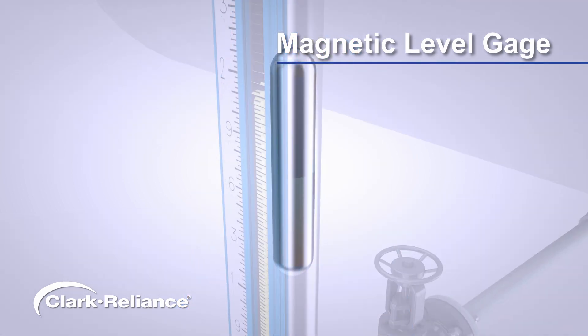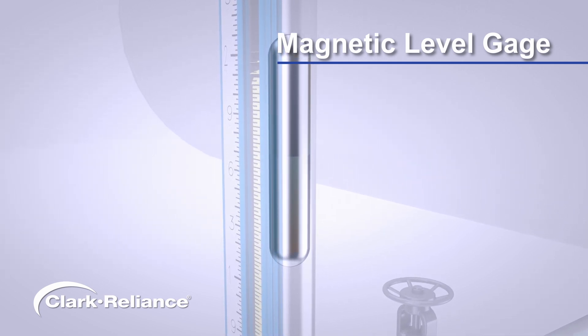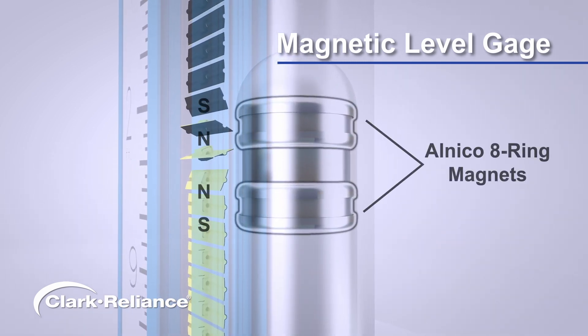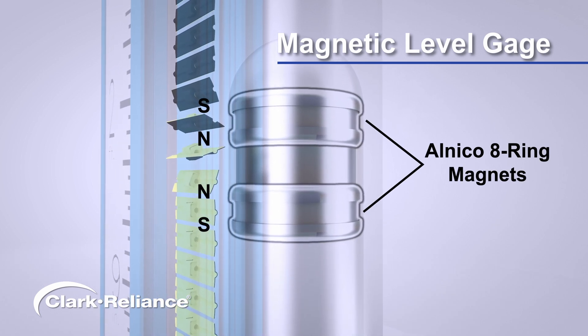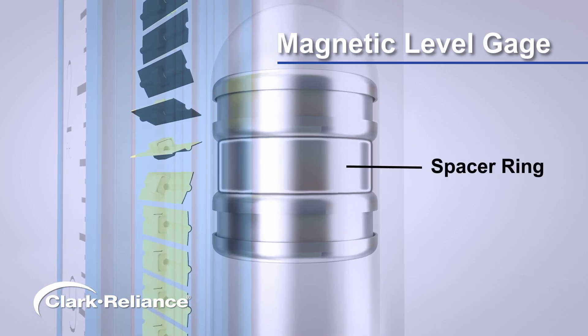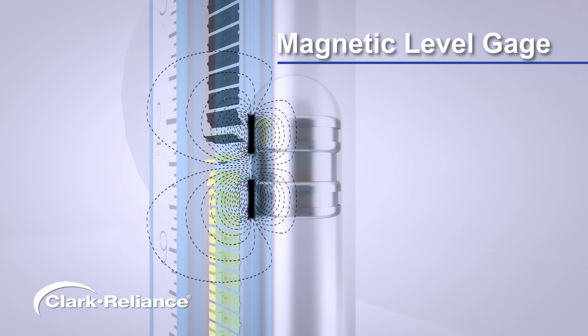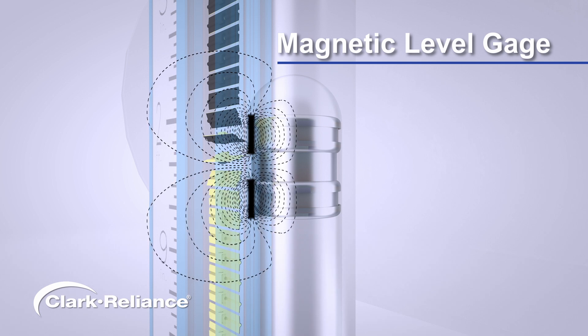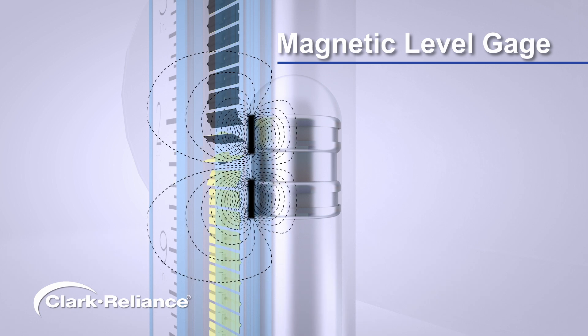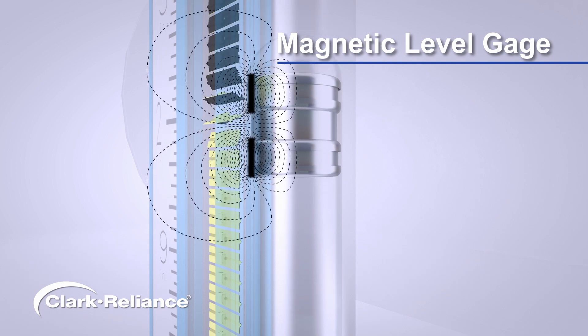The Jerguson float design features the strongest magnetic field of any magnetic level indicator, due to its unique construction. Two high-grade Alnico eight-ring magnets, with north poles opposing, are locked in place separated by a spacer ring. Magnetic flux flows from the north pole to the south, and since magnetic flux lines cannot cross, a dense signal is projected around the float, creating a strong magnetic coupling between the float and indicator.